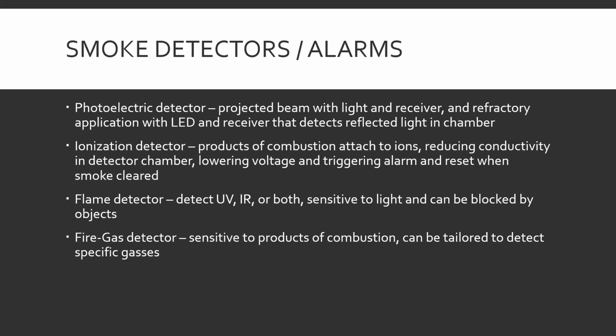That's because normal air is pretty clean. Not a lot of particles in there. And there's a little amount of radioactive material in a smoke detector. And so that's kind of energizing the air, turning it into ions. And so the smoke detector can read these ions and their electrical current in the detector and go, all right, everything's within normal limits, nothing to worry about. When smoke particles or other particles in there, like a lot of dust, get in there, whether it be the dust or the smoke particles, they attach to the ions, and then suddenly there's less of these ions that are freely bouncing around, or as often. That lowers the voltage to the receiver, and the smoke alarm goes, uh-oh, the voltage has gone down. I have to sound an alarm because it's outside of normal levels.